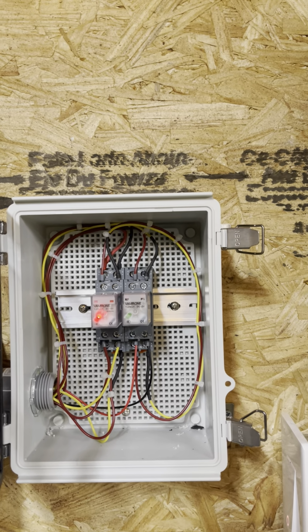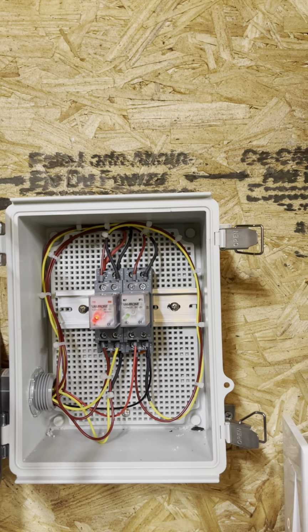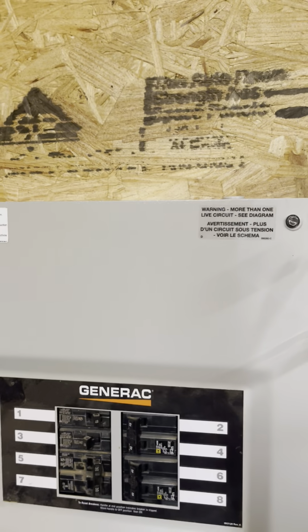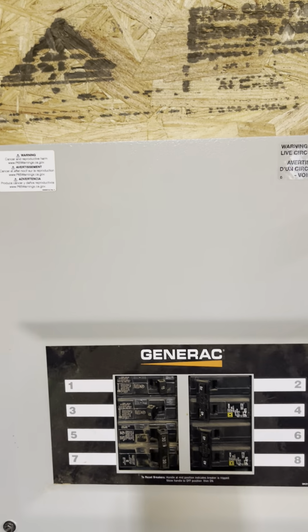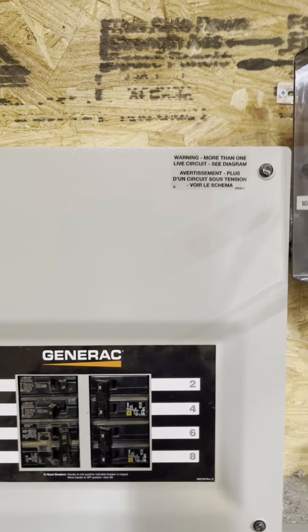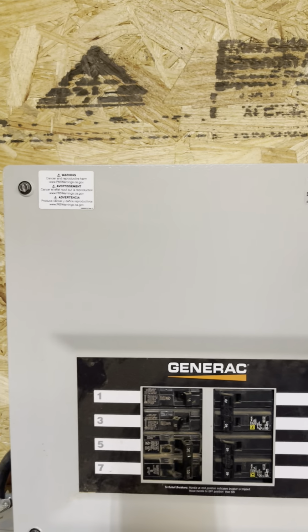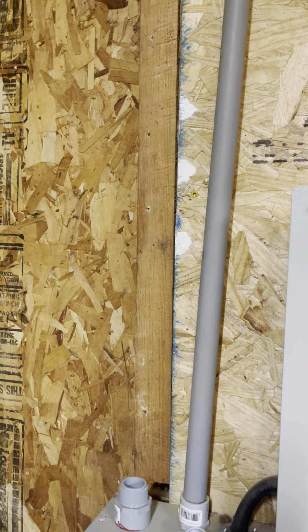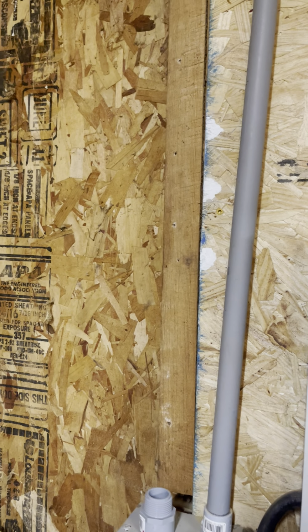You can see I'm still calling for both up. The inverter realized, hey, I've got real power back, so it shut off. It says I don't need the generator. The generator will stabilize and make sure it has voltage, then switches back. I don't know if you heard that click, but it switches back. And now the generator will run about a 30-second cool down cycle, and then it will shut off and be prepared for the next time.